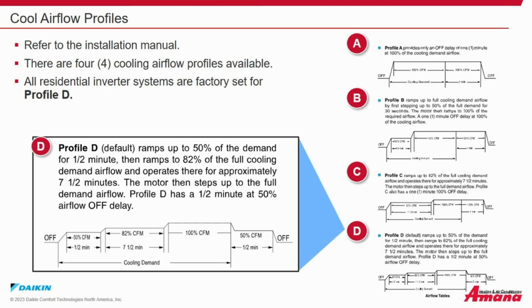Profile D, which is default, ramps up to 50% of the demand for 1/2 minute. Then it ramps up to 82% of the full cooling demand airflow and operates there for approximately 7.5 minutes. The motor then ramps up to full demand airflow. Profile D has a 1/2 minute at 50% airflow off delay.